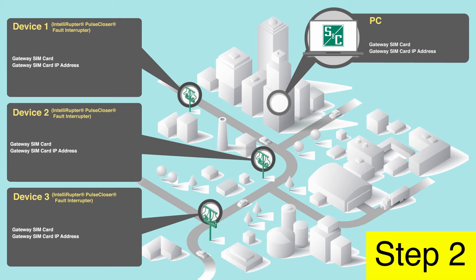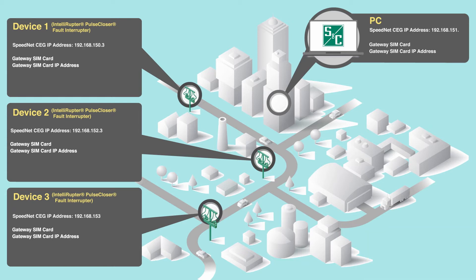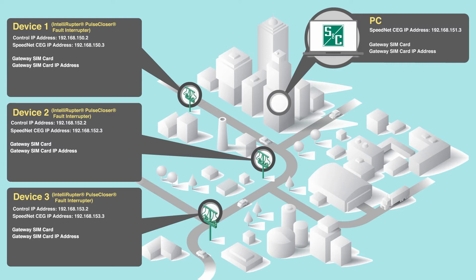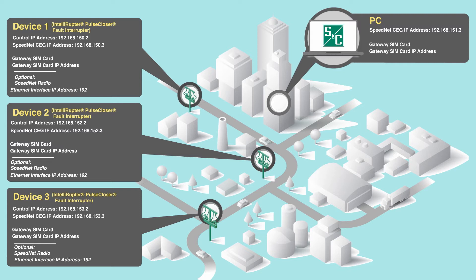Step 2: For each gateway to be used on the cellular network, select a unique IP address. Step 3: Because Intelliruptor Pulse Closer Fault Interrupters have their gateways factory installed and wired, use the subnet of the gateway's IP address to assign a unique IP address to each Intelliruptor Fault Interrupter. Optionally, when using the cellular network in conjunction with a Speednet radio network, use the subnet to assign a unique IP address to each radio.